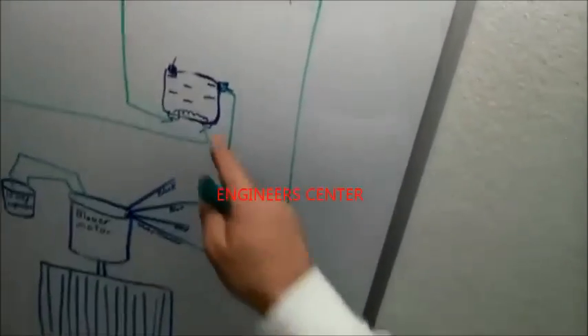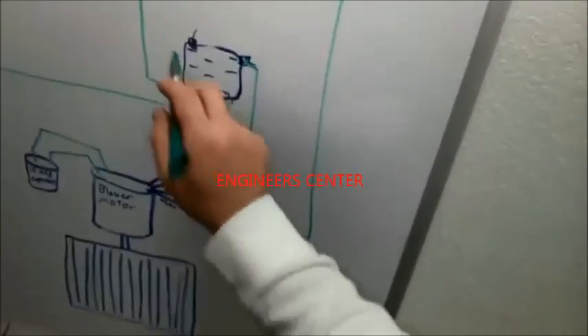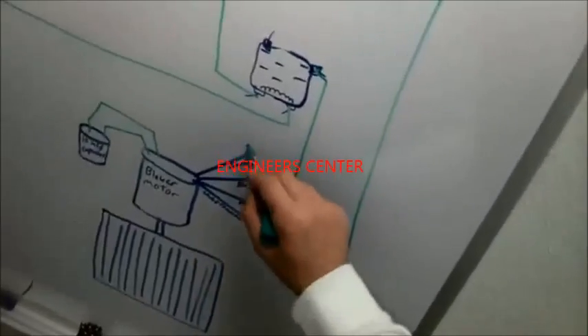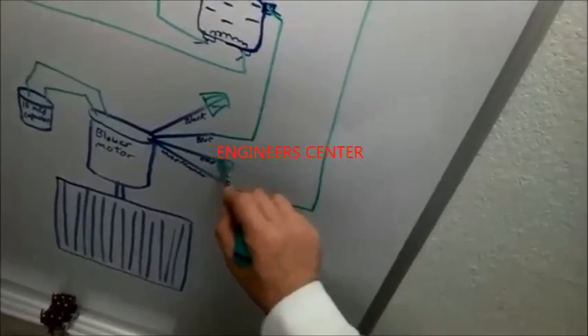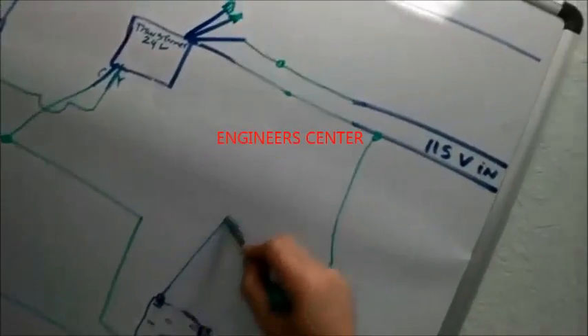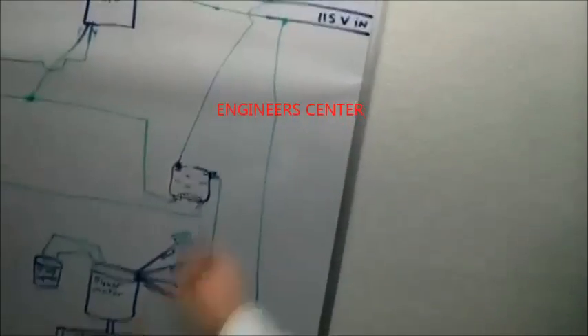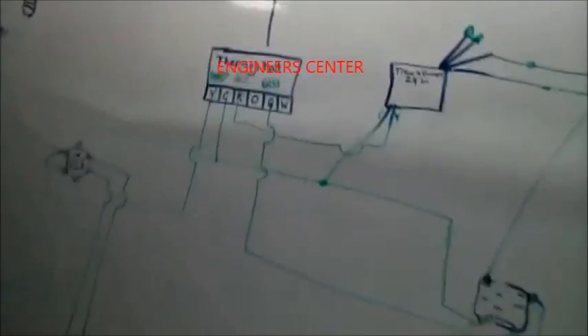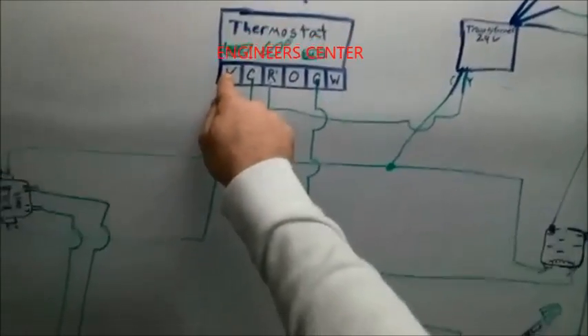Now, since this is just a simple basic one-speed unit, we're going to go ahead and choose medium speed, blue here, to use. And so we're going to give blue, bam, right to the fan relay, the normally open terminal, because when I energize it, it's going to close, and so it's going to energize. We're going to cap these ones off. Now this one, of course, needs to get power from that side. So now our blower motor will get both sides of power when it turns on, because it's getting one side all the time, and the other side it'll get from this fan relay when the thermostat is turned on into cool. A thermostat in the cooling mode has yellow and green jumpered inside for a single stage unit.